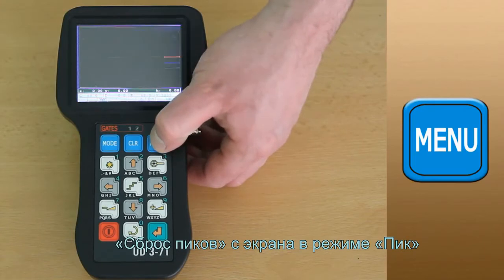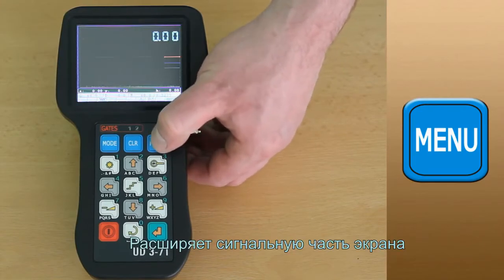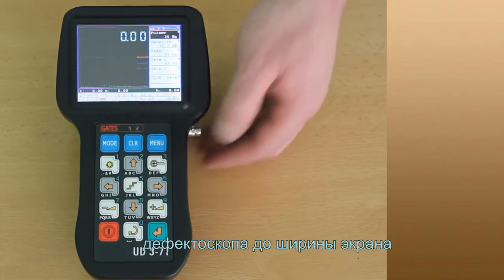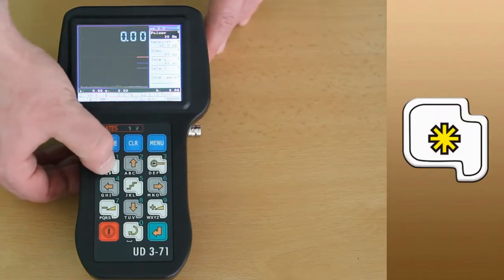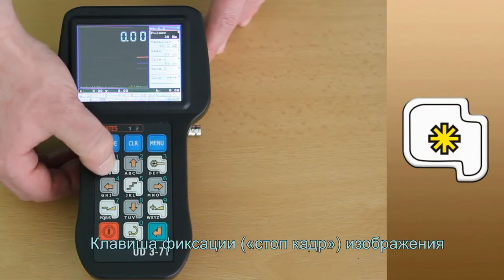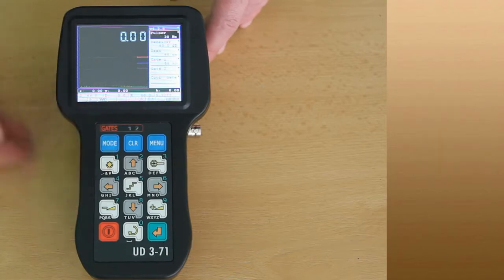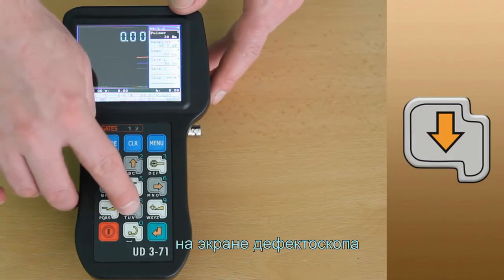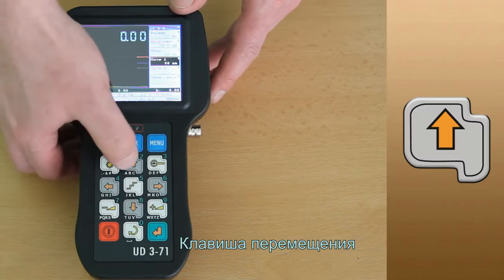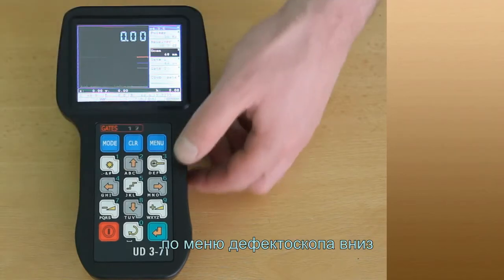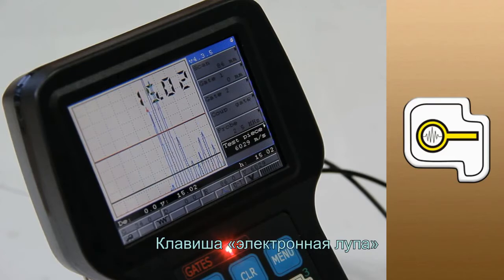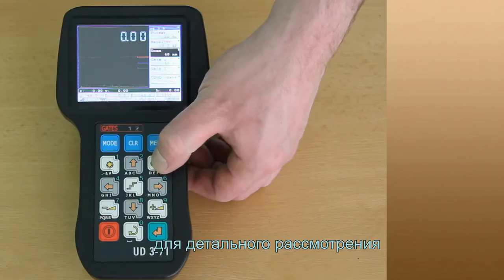Use menu key to widen the signal zone of the flaw detector screen. Use freeze frame key to fixate the image on the flaw detector screen. Use down arrow key to scroll down through the flaw detector menu. Use up arrow key to scroll up through the flaw detector menu. Electronic magnifying glass key is used for detailed examination of the signal shaped on the flaw detector screen.